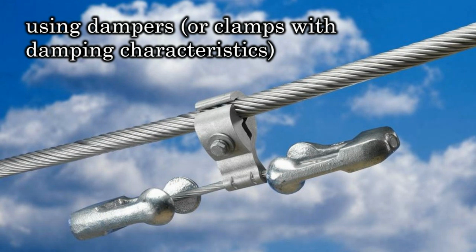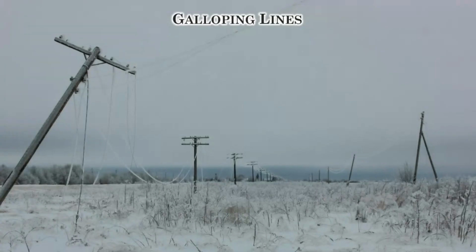This vibration of the conductor is an energy. Energy is traveling through the conductor. So when you provide something that can dissipate this energy by movement, by heat absorption, by anything like this, you are reducing the effect of this energy on your conductor. And normally this is clamped near the connection point of the conductor, near the fixing point, close to the insulator.